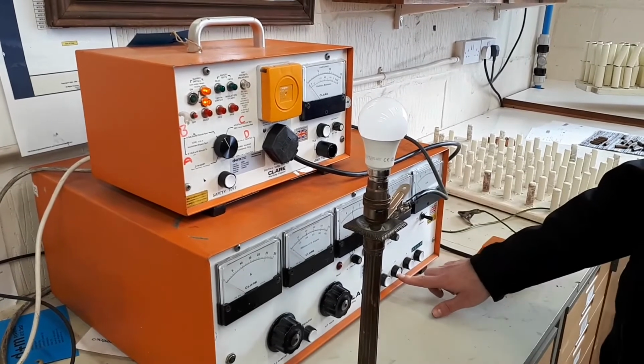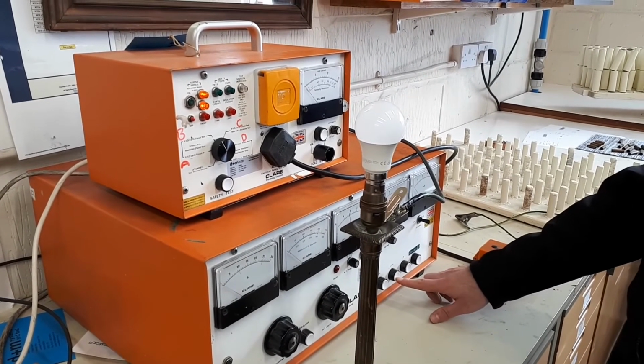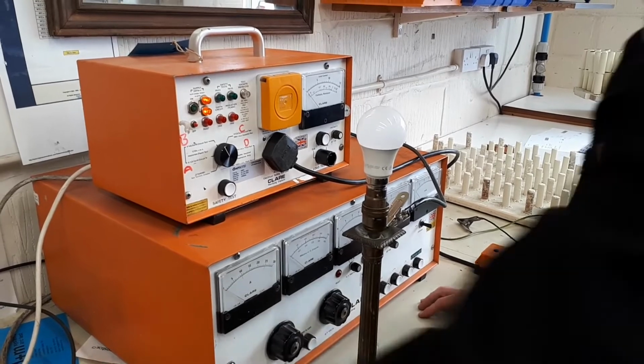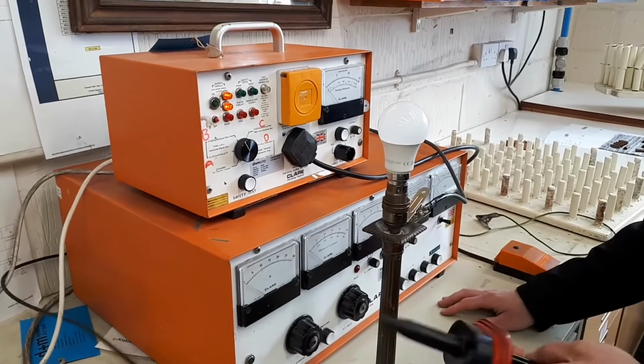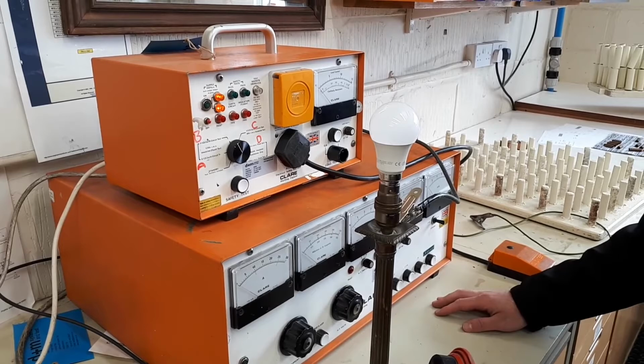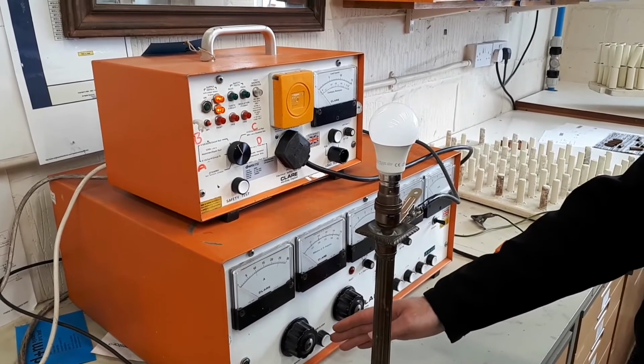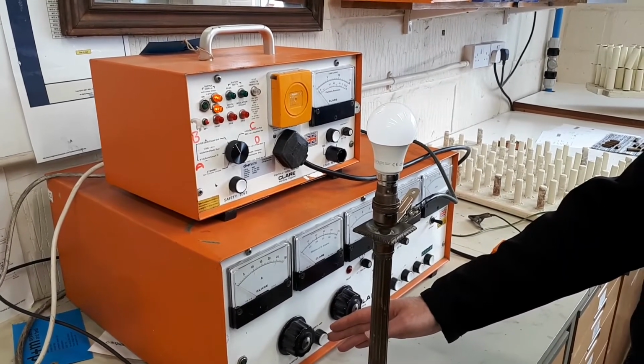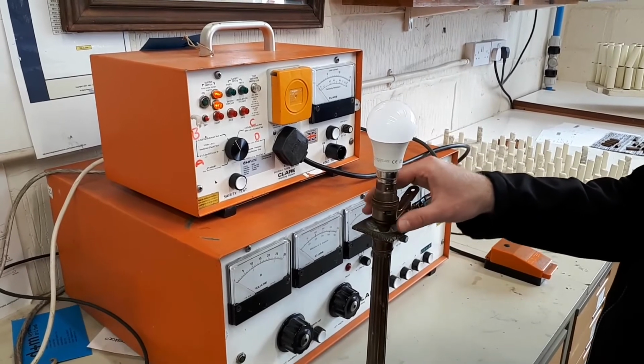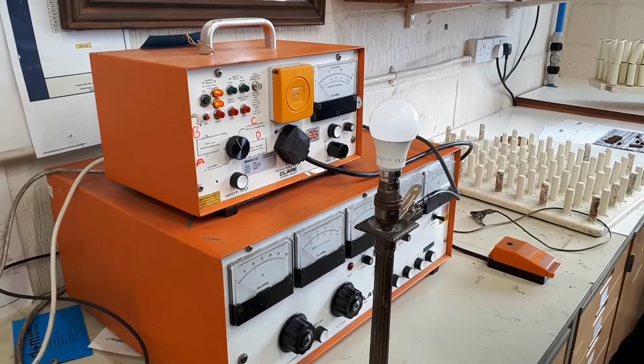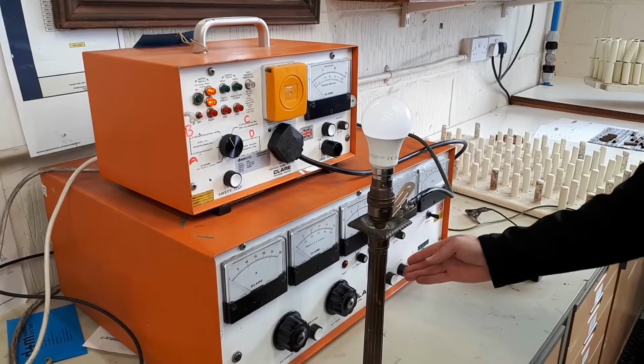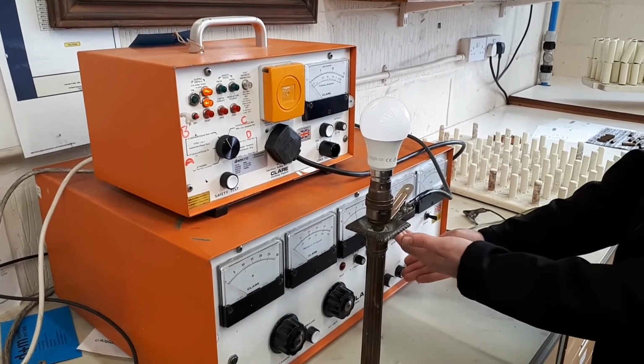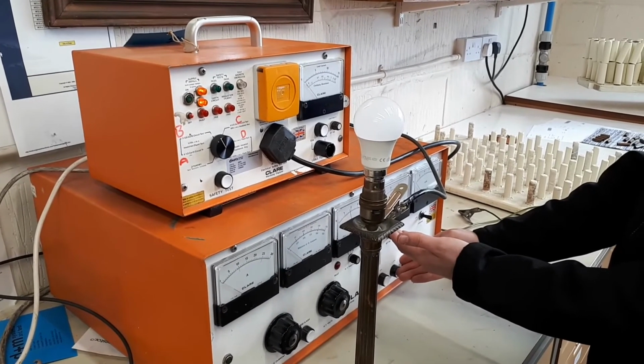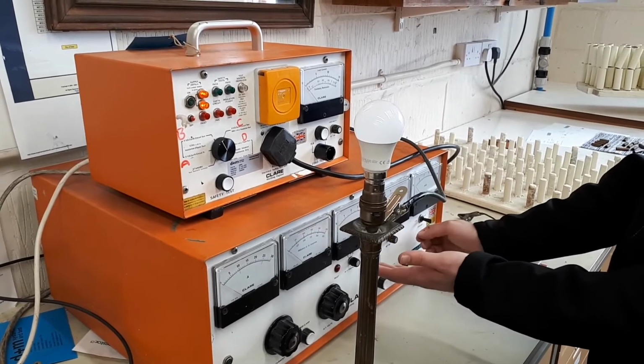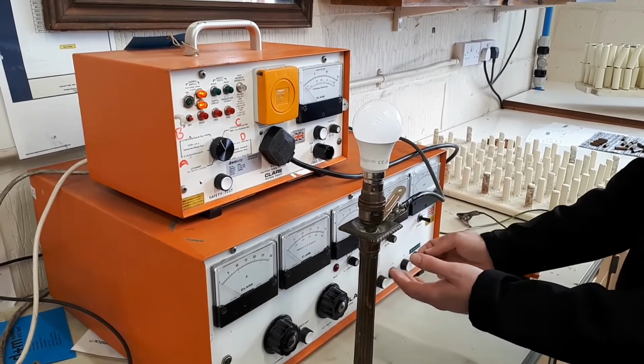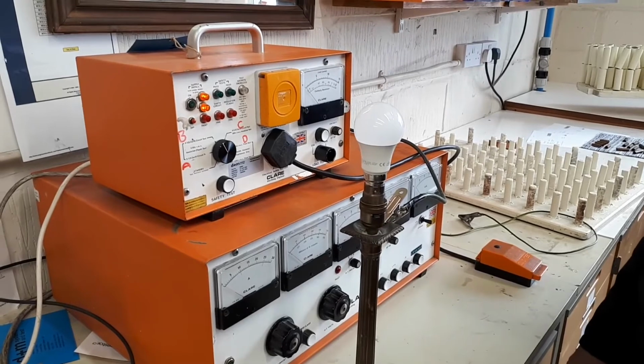For class 2 light fittings, it's 3750 volts, and we test this using the earth probe on the exposed metal parts. Ensure that any switches on the fitting are on during this test. The leakage current should not exceed 5 milliamps. If the test fails, the alarm will sound and the voltage will switch off. Do not hold or touch the fitting during this test, as it is hazardous.